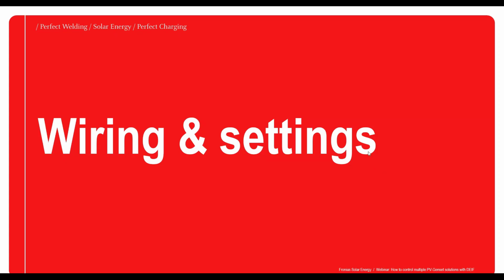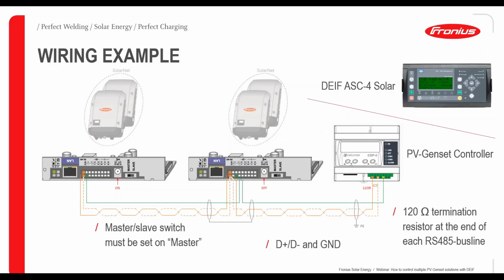So, yeah, thank you, Alan, so far for introducing us into the DEIF topics, the DEIF components. Now I quickly want to show you some wirings and some examples, how you can do that and what to look out for. What we can see on this picture is the actual Modbus RTU communication between the Fronius data managers and the controlling, which can be either the PV-Genset controller from Fronius or the ASC4 Solar from DEIF. It's connected via Modbus. And above the data managers, multiple inverters are symbolized.